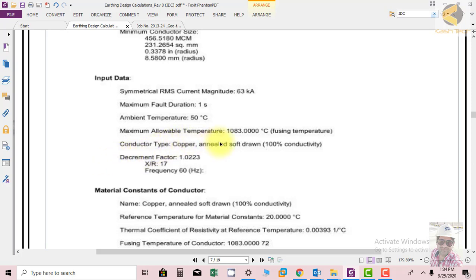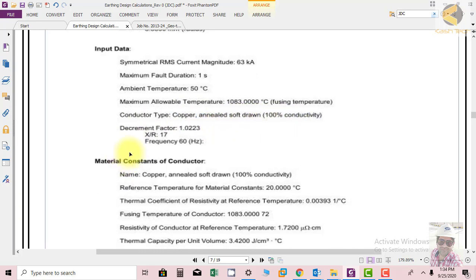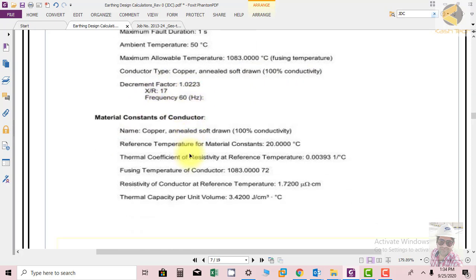Maximum allowable temperature is 1083, which is basically the fusing temperature of copper. Conductor type copper, 100% conductivity, decrement factor 1.0223, X over R ratio is 17, frequency 60 Hertz. Material constant of conductor: name is copper annealed soft drawn, resistivity reference temperature for material constant is 20 degree centigrade, thermal coefficient of resistivity at reference temperature is 0.00393 per degree centigrade.